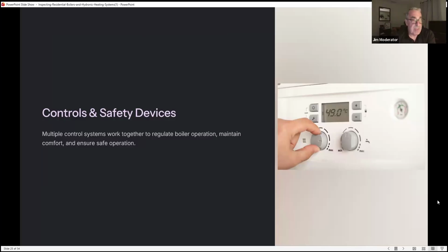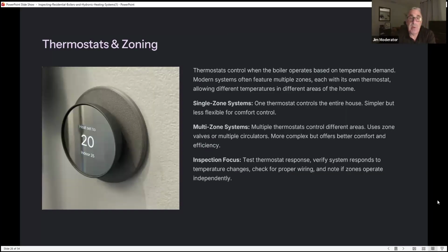Safety controls and devices. Multiple control systems work together to regulate boiler operation, maintain comfort, and ensure safe operation. Thermostats and zoning. Thermostats control when the boiler operates based on temperature demand. Modern systems often feature multiple zones, each with its own thermostat, allowing different temperatures in different areas of the home.